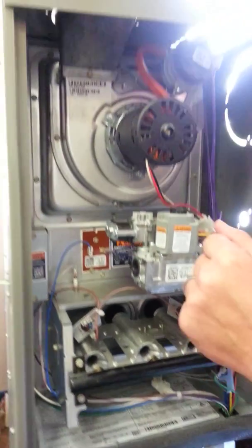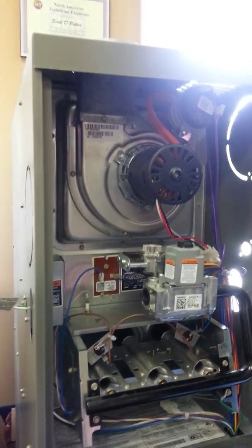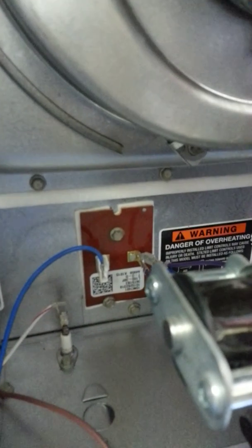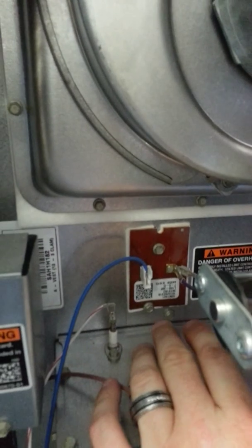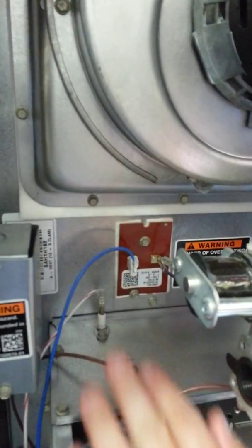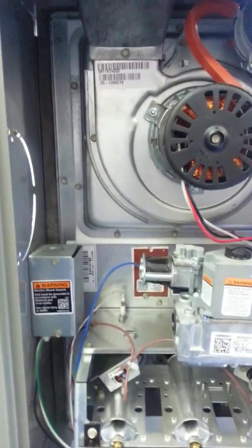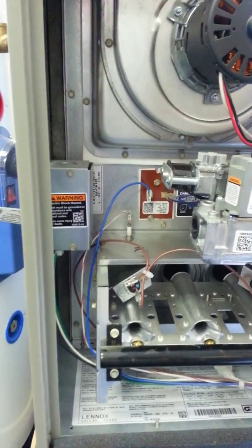Now, a few more safety features. If the blower fails to blow, something happens, the motor's burned up. There's a high temperature switch right here, a little rod about 5 or 6 inches long. It senses the heat by temperature, and if it overheats, it shuts the whole thing down.